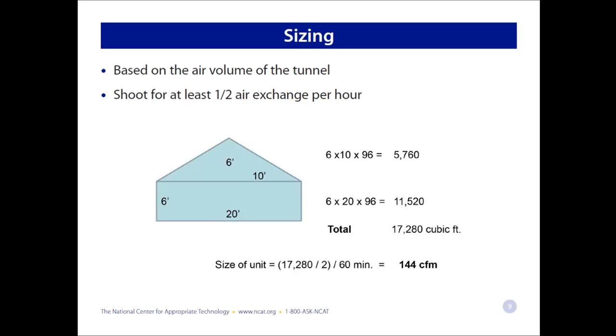So first I broke the tunnel into two different sections, so it was easy to determine the volume of air in each section, and then added those two together. And you can see here, I came up with just over 17,000 cubic feet of total air volume inside each of these tunnels. So to size the unit, I was shooting for at least one half of an air exchange of the total volume of air per hour in the tunnel. And that was, like I said, a little bit arbitrary, but it seemed like a good place to start.